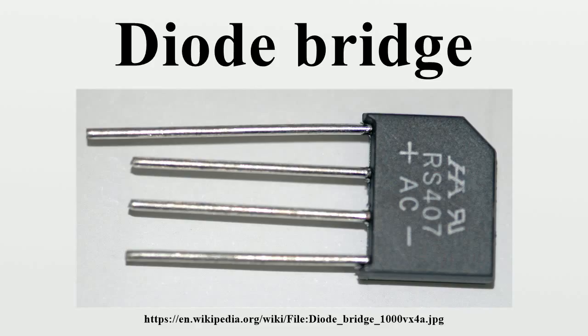If the normal load cannot be guaranteed to perform this function, perhaps because it can be disconnected, the circuit should include a bleeder resistor connected as close as practical across the capacitor. This resistor should consume a current large enough to discharge the capacitor in a reasonable time, but small enough to minimize unnecessary power waste. The capacitor and the load resistance have a typical time constant τ equals RC, where C and R are the capacitance and load resistance respectively.